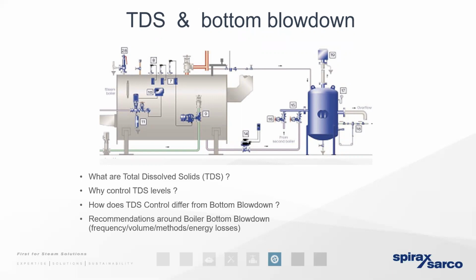The sugar will dissolve. Keep adding sugar, keep adding sand, and we know that over time the sand is going to occupy a lot of the volume within the cup, but the sugar will continue to dissolve. And that's kind of the same as what's happening with the minerals and chemicals that are present in the raw water and that are being added into the boiler. So as water is being evaporated and steam's being produced, we find that the chemicals that are held in solution, the TDS, the sugar in our analogy, it gets more and more concentrated. It's going to produce foaming.